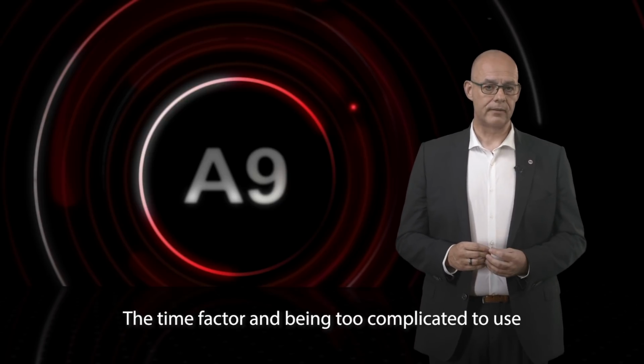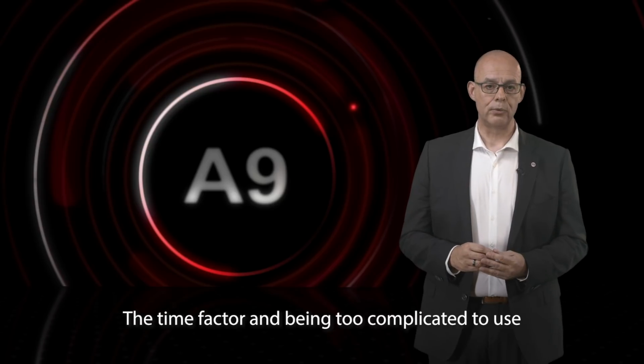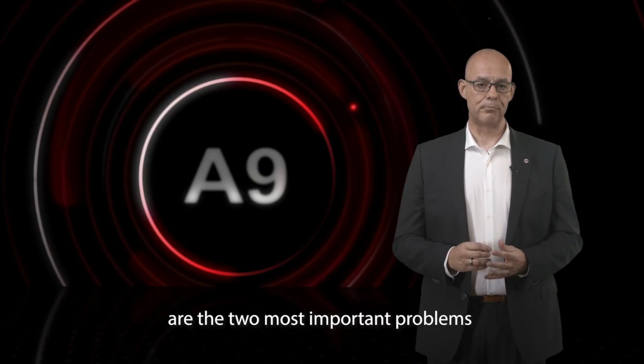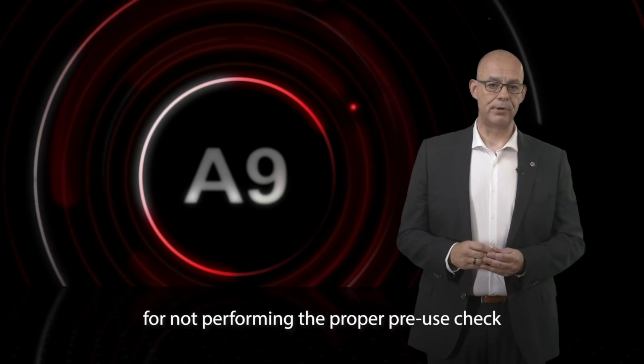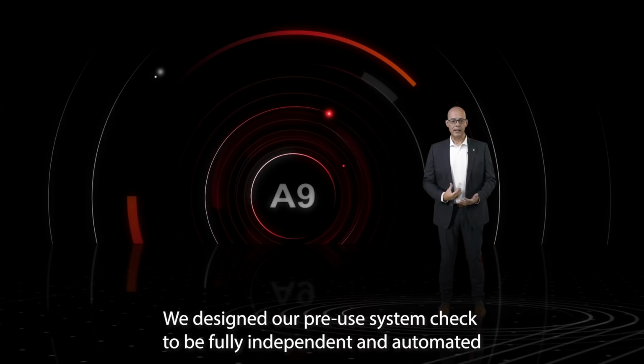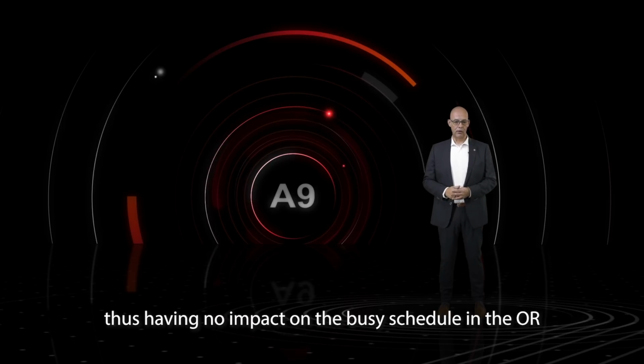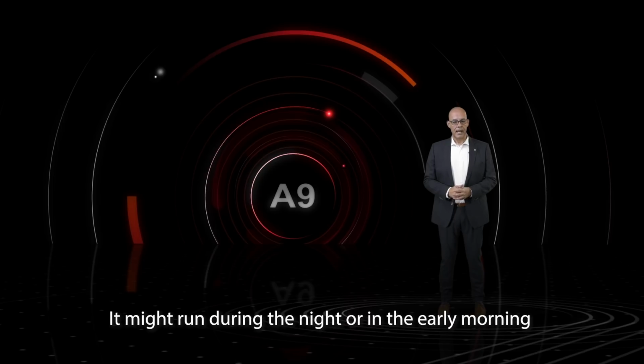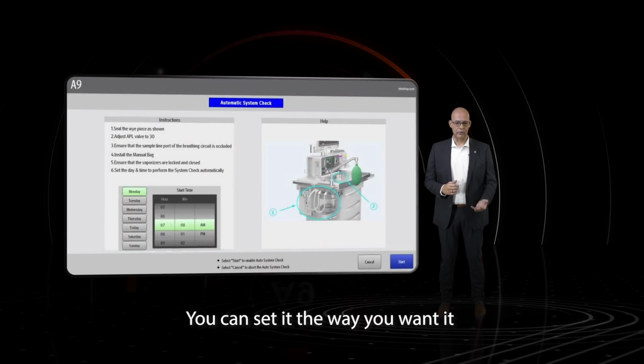The time factor and being too complicated to use are the two most important problems for not performing the proper pre-use check. We designed our pre-use system check to be fully independent and automated, thus having no impact on the busy schedule in the OR. It might run during the night or in the early morning. You can set it the way you want it.